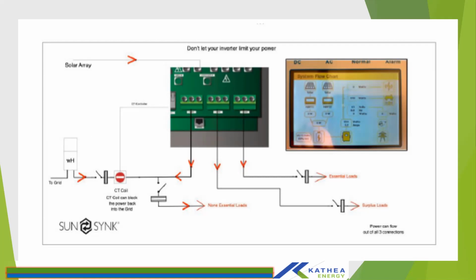However, if there is excess or surplus from PV or battery after supplying essential loads, then the system would simply use this port as an output to push back power through backfeed to your non-essential loads. That is your high power loads. And then the meter is there to monitor, in cases of zero export, that power is not fed back to the grid. It's only supplied for self-consumption. So basically the CT gives the reference for the inverter to produce the set point for the inverter.